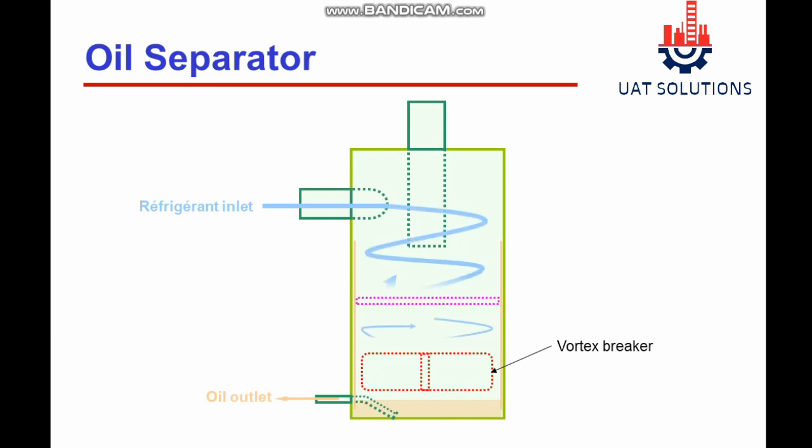Even though the openings between the separation chamber and the sump chamber are small, the vapor, liquid refrigerant, and oil will tend to continue to swirl in the sump chamber. Less violent activity is desired in the sump chamber to minimize oil droplets from being swept back into the separation chamber.